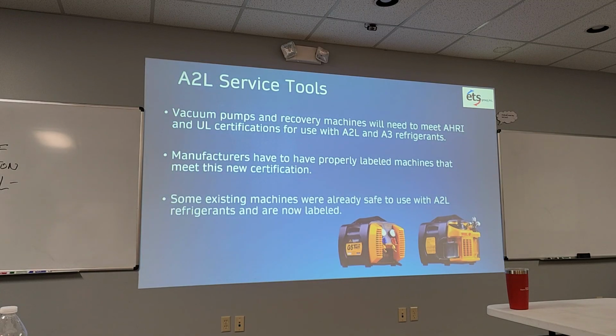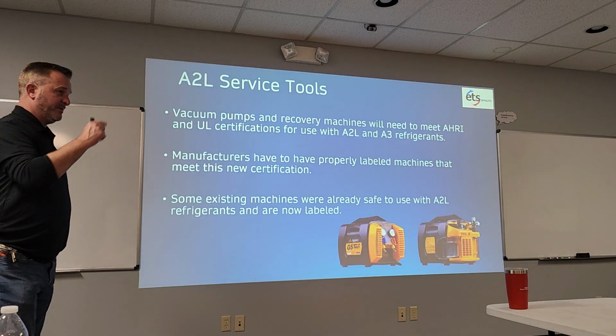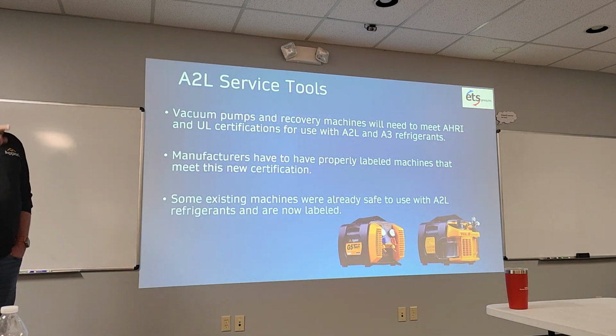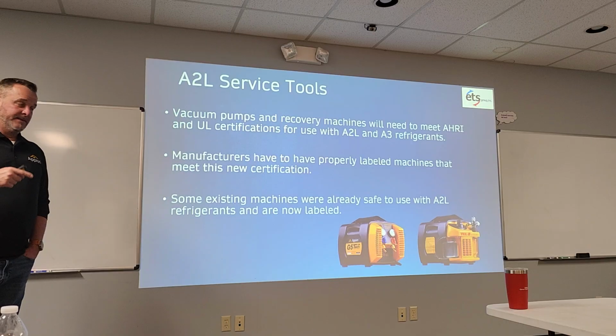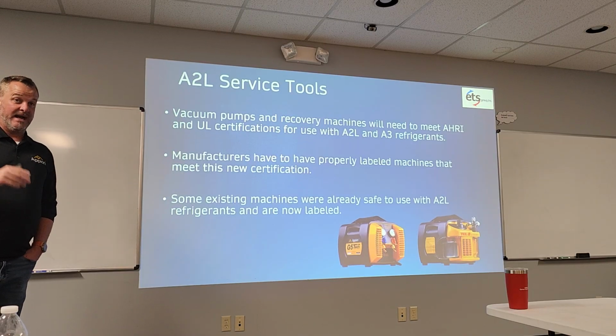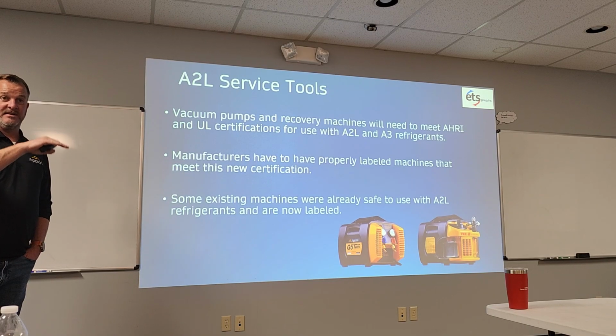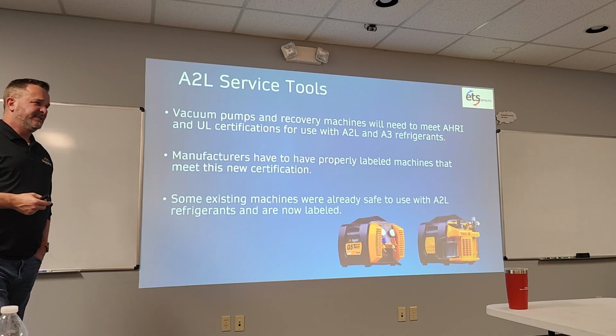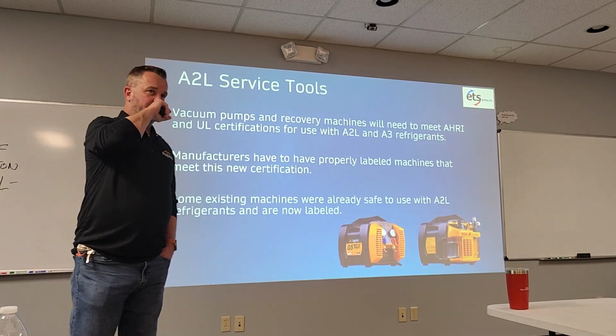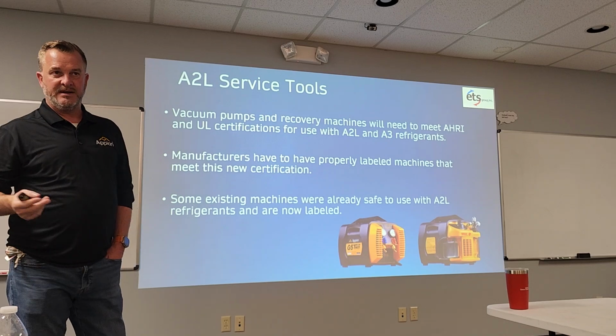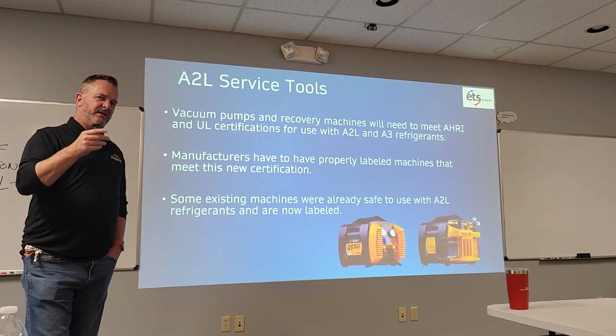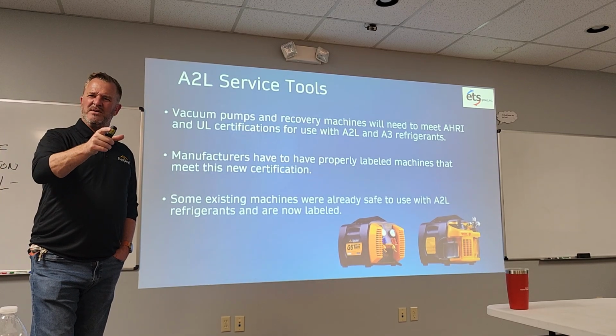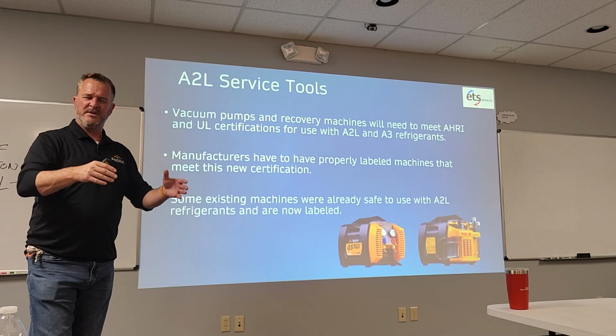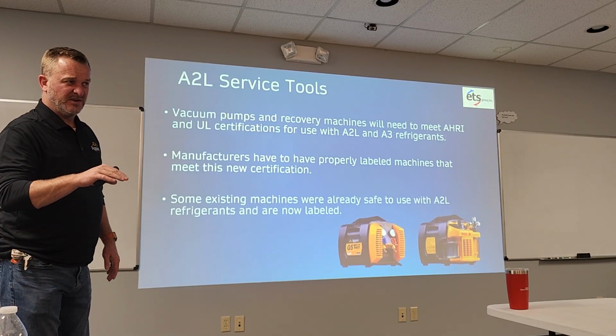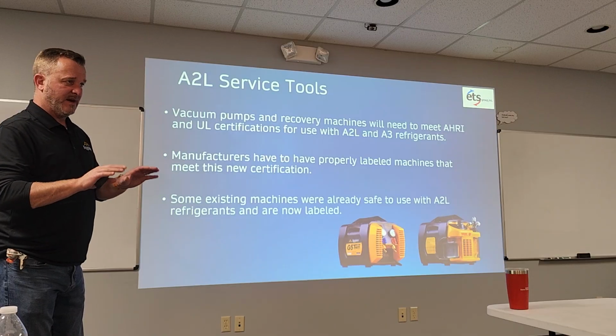As we said before, vacuum pumps and recovery machines need to meet AHRI and UL certifications for use with A2L and A3 refrigerants. Now the one thing I want to tell you is do not recover A3 refrigerants. There's not a recovery machine out there, at least in this class of recovery machines, made for A3 refrigerants. I once had a distributor in Michigan call and ask if they could recover A3s. I said absolutely not. They sent me a picture of what I think was a Master Cool recovery machine, a small unit that claims to be good for A3s and A2Ls, but I'm telling you right now, you do not want to recover A3 refrigerants.